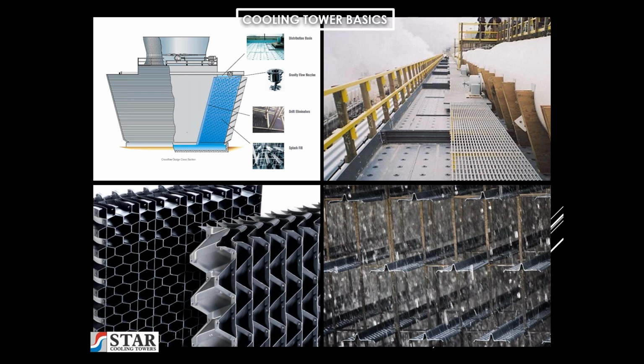On all the large cross-flow towers, there's splash fill, and it can consist of wood lath, or it could be 4-inch wide, 6-inch, or 8-inch wide formed PVC splash bars. These splash bars are evenly spaced horizontally and vertically, typically 8 inches vertical by 8 inches horizontal, and can be installed either perpendicular to the airflow or parallel to the airflow. The air inlet louvers are designed to retain the water in the cooling tower and equalize the air into the fill area.